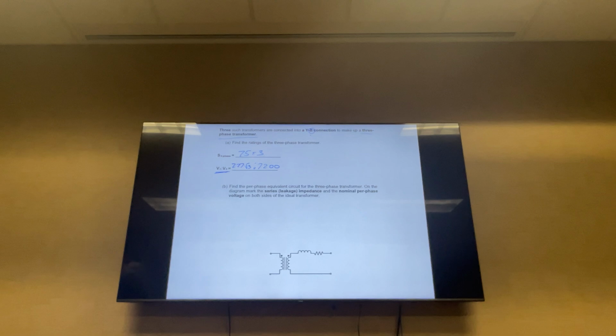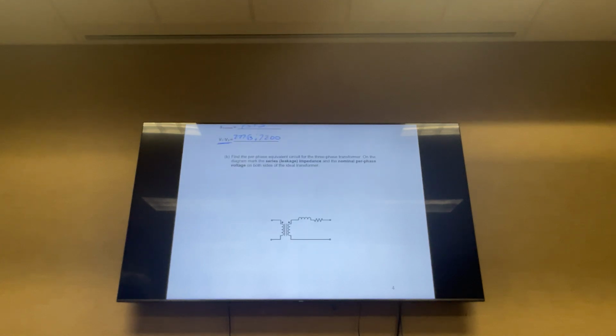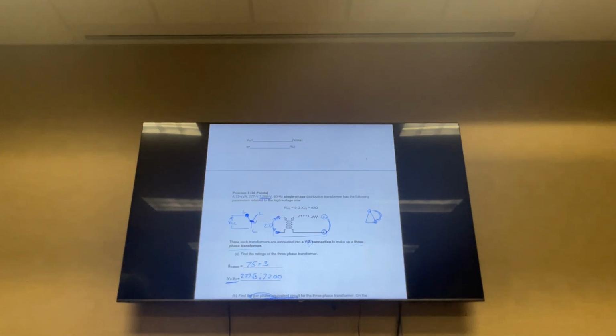And then the per phase equivalent circuit. So the per phase equivalent circuit, of course, on the diagram, mark the series leakage impedance, okay? Nominal per phase voltage. So this is, of course, where I was drawing the per phase equivalent circuit, and that's my Y equivalent. So if I want to write out what the actual nominal voltages here are, they would be the line to line divided by square root of 3 on both sides, since this is a line to neutral equivalent. Then the only unknown here is this impedance.